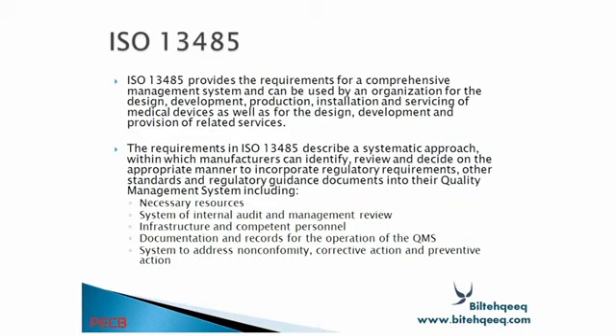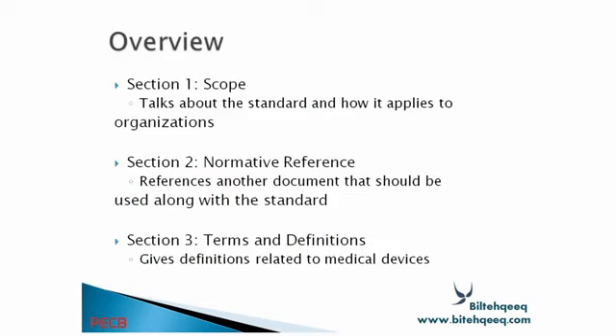ISO 13485 provides requirements for a comprehensive management system and can be used by an organization for design, development, production, installation and services of medical devices, as well as for the design, development and provision of related services. The requirements describe a systematic approach in which manufacturers can identify, review and decide on the appropriate manner to incorporate regulatory requirements, other standards and regulatory guidance documents into the quality management system. This includes resources, system of internal audit and management review, infrastructure and competent personnel, documentation and records for operation of the quality management system, system to address non-conformity, corrective action and preventive actions.